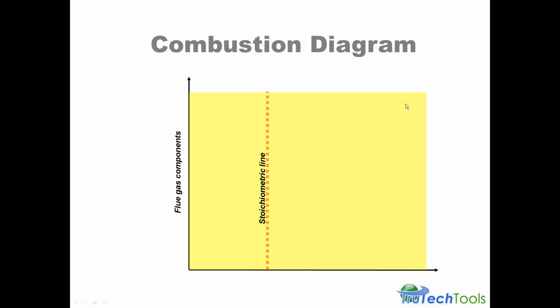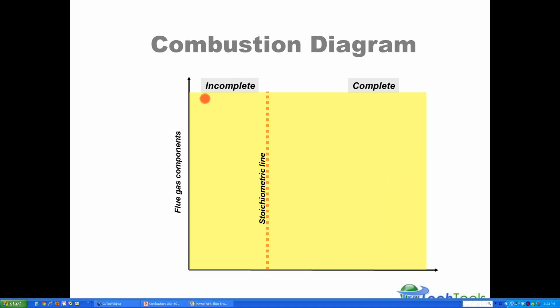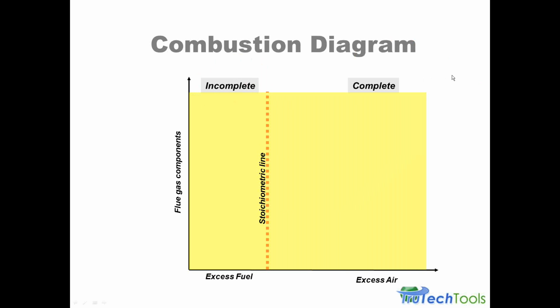But since we don't have that, we'll be looking on both sides of that line to talk about incomplete combustion. So we have incomplete on the left side, and by incomplete in this case we mean not enough oxygen available for the full combustion. It can also be termed the excess fuel side, more fuel than oxygen. And on the right hand side, complete combustion. Now on this side we will also see excess air, or excess amounts of oxygen, that will be showing up when the combustion analyzer is doing its test.